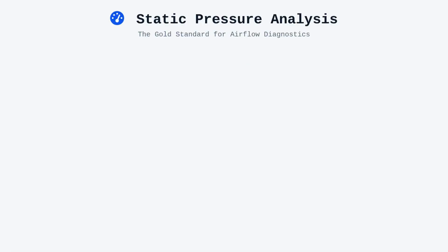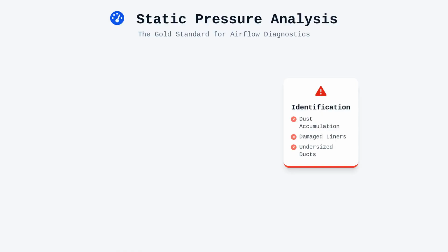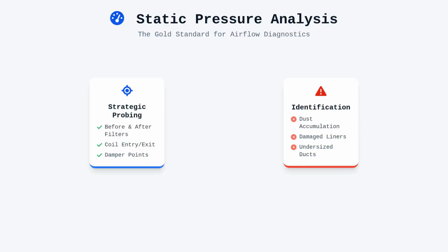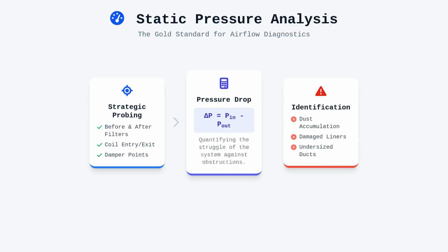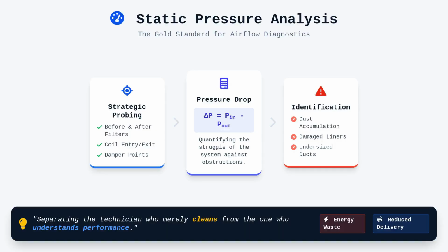Static pressure measurements are the primary diagnostic method for identifying airflow restrictions, such as heavy dust accumulation or damaged internal liners. By placing probes at specific points, typically before and after filters, coils, or dampers, we can calculate the pressure drop across these components. If the observed drop exceeds the manufacturer's specifications, we know we have an obstruction that the system must overcome, costing the user energy and reducing air delivery. This is where your math skills become critical, as these measurements allow you to quantify exactly how much a system is struggling. It is a fundamental troubleshooting step that separates a technician who merely cleans from one who understands system performance.